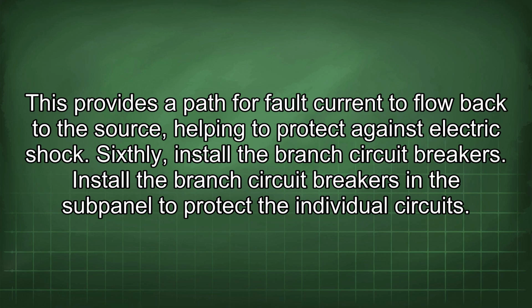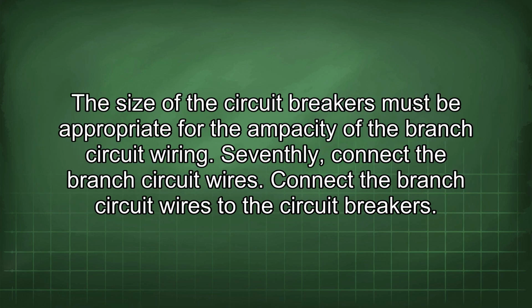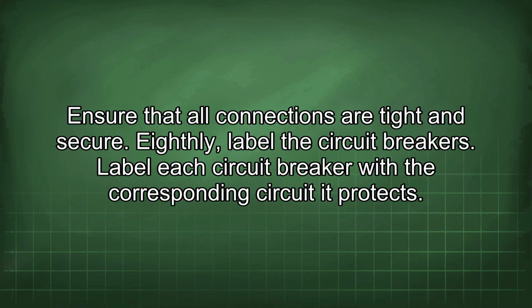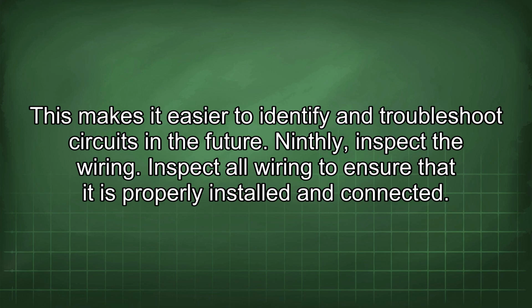Sixthly, install the branch circuit breakers. Install the branch circuit breakers in the sub-panel to protect the individual circuits. The size of the circuit breakers must be appropriate for the ampacity of the branch circuit wiring. Seventhly, connect the branch circuit wires. Connect the branch circuit wires to the circuit breakers. Ensure that all connections are tight and secure. Eighthly, label the circuit breakers. Label each circuit breaker with the corresponding circuit it protects. This makes it easier to identify and troubleshoot circuits in the future.